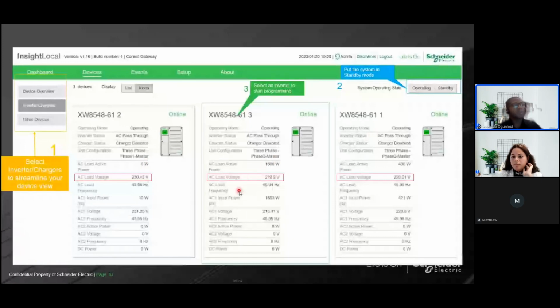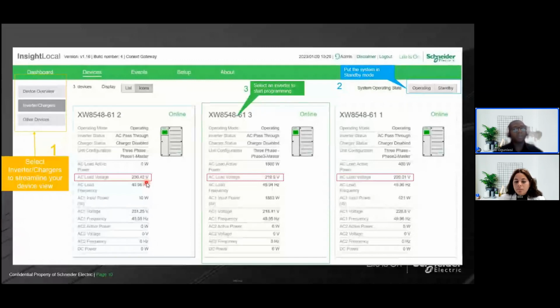This is also a very critical moment for you to know your AC output voltages, because you have to do some sort of calibration if it's not done already. With the older units, the XW pluses, you had to use the configuration tool - some people might know that, some might not. This was a device that lets you connect to the system and program the output voltage you want. So let's say you have 230 volts here, but we're seeing completely different voltages here. This would have been an issue if we had six inverters.